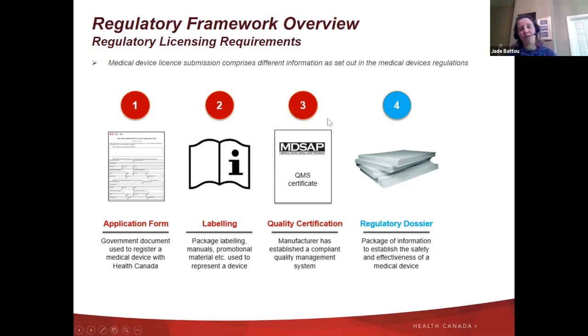They also have to supply a quality management certificate, which is the ISO 13485. This is to confirm that the device is designed and manufactured following this ISO, and it has to be MDSAP certified, which is the Medical Device Single Audit Program.